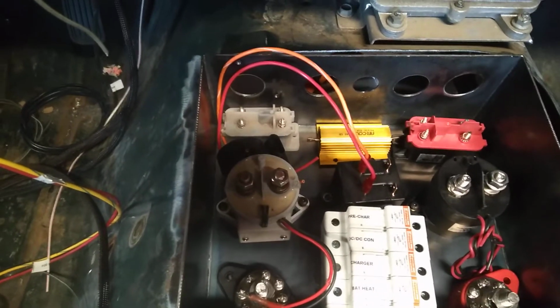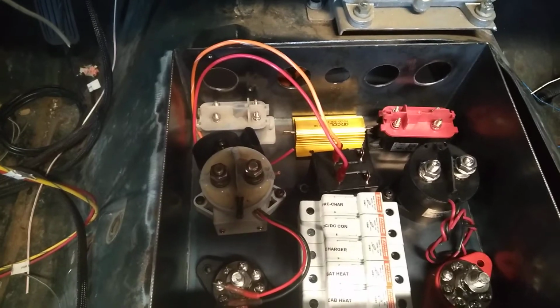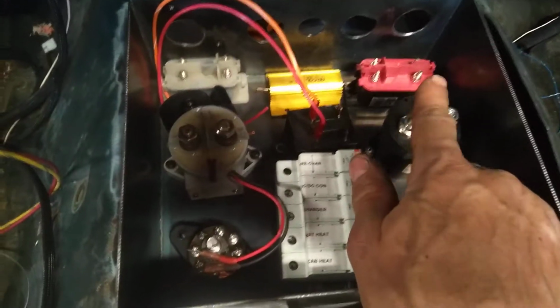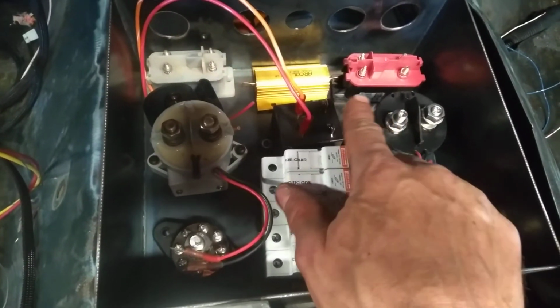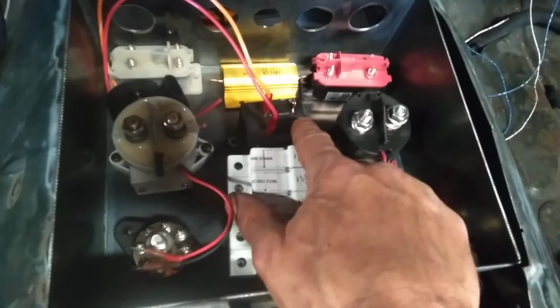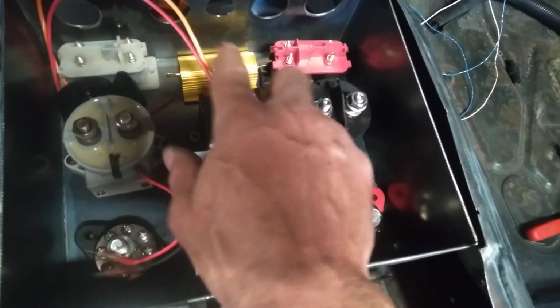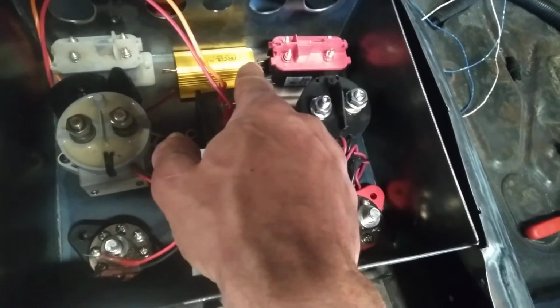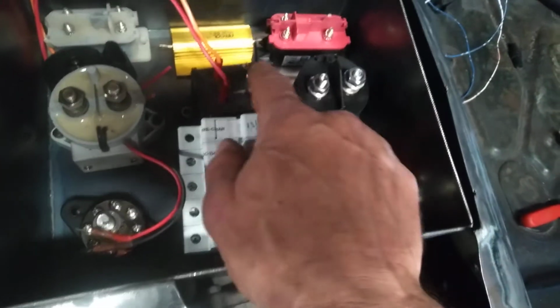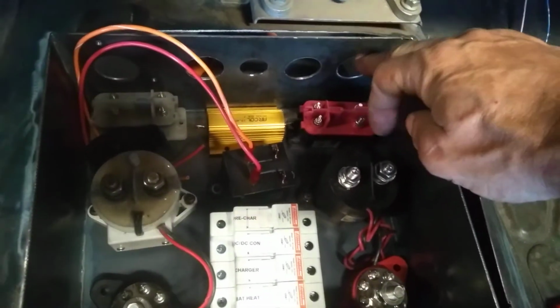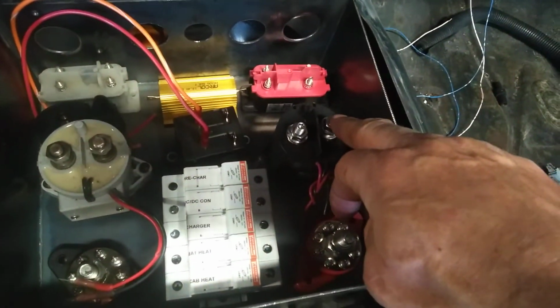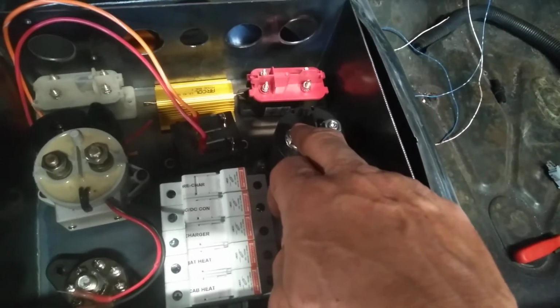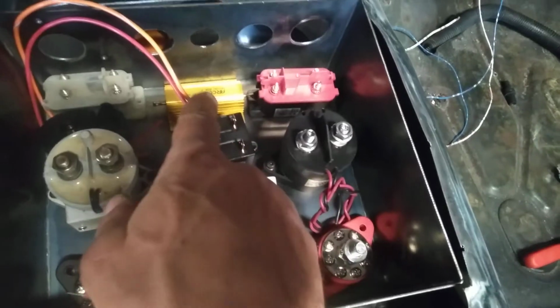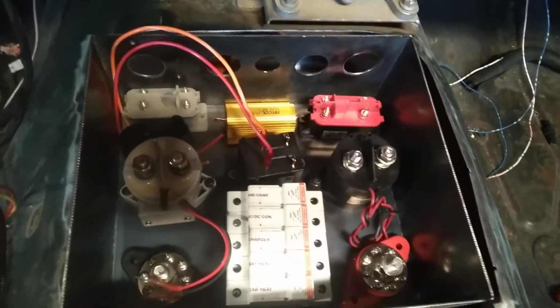The little gold dealie back there is a resistor. So this pre-charge thing, what it does is one wire will come from here and go into this contactor, then come out of this contactor, go into that side of the resistor, come out of the resistor on that side, and then go to the other side of the contactor. When this contactor is energized, it'll complete that circuit, and then power from the most positive battery terminal here will go through the resistor over to the motor inverter, out the motor inverter, and through that resistor will slowly charge up those capacitors.